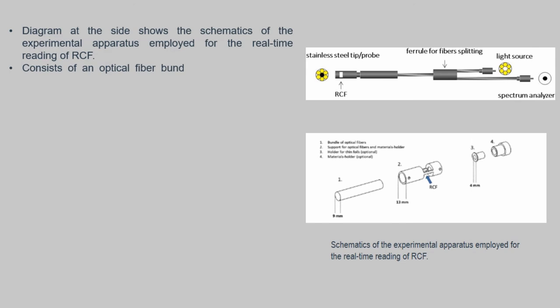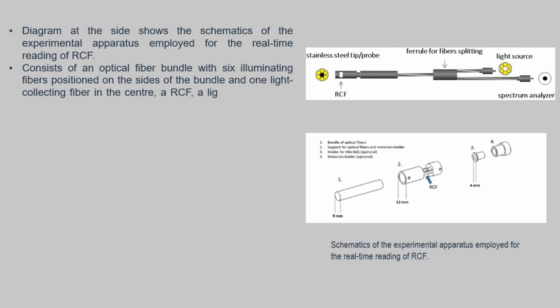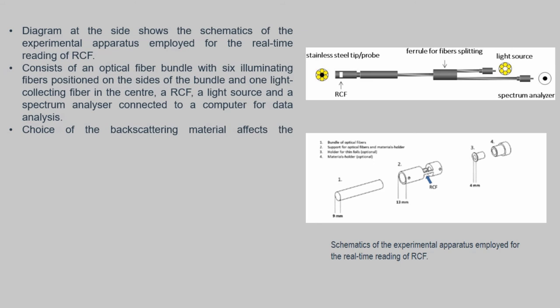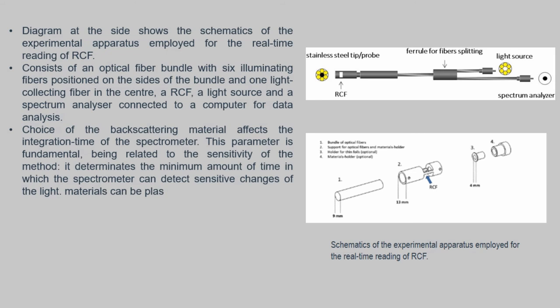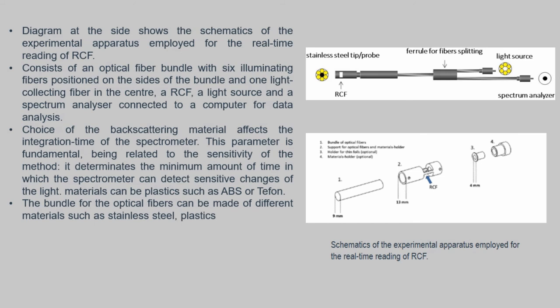The diagram shows the schematic of the experimental apparatus employed for the real-time use of the radiochromic film (RCF). It consists of an optical fiber bundle with 6 illuminating fibers positioned on the side of the bundle and 1 light-collecting fiber in the center, the RCF, a light source, and a spectral analyzer connected to a computer for data analysis. The choice of the backscattering material can affect the integration time of the spectrometer — a parameter fundamental to the sensitivity of the system. The material can be plastic such as ABS, while the bundle of optical fibers can be made of different materials such as stainless steel or plastic, which have less scattering with ionizing radiation.